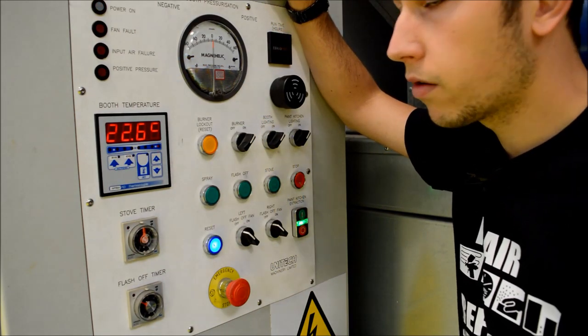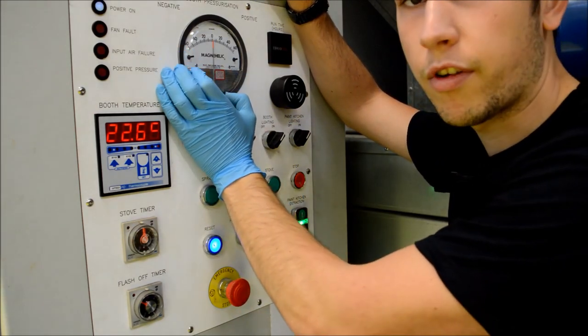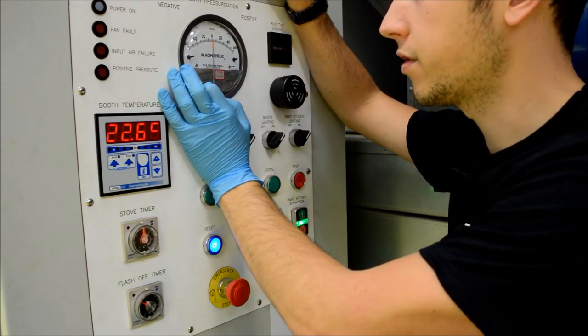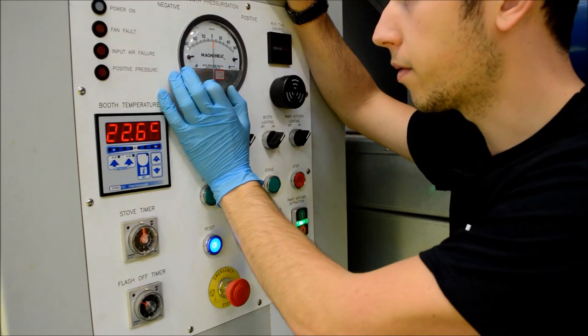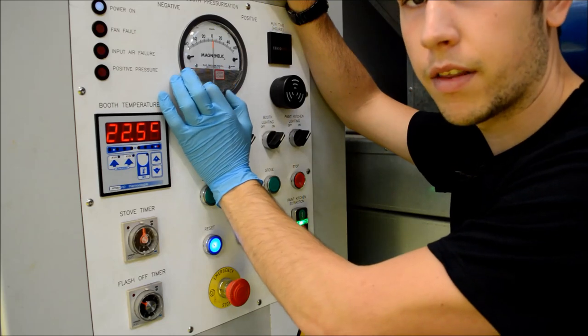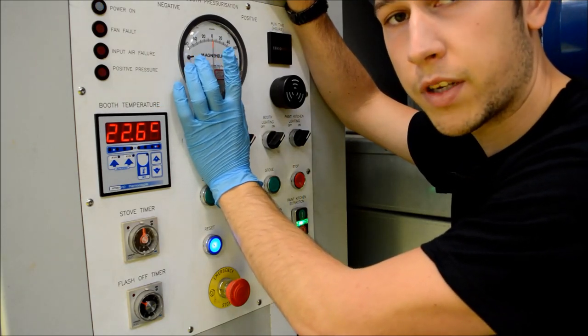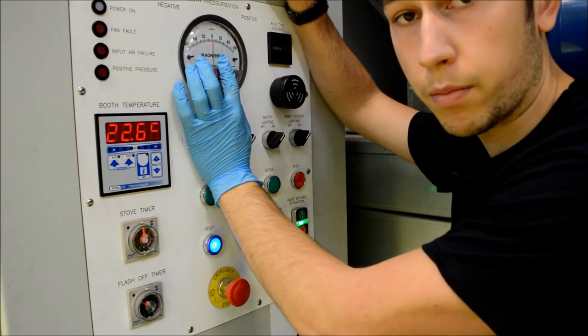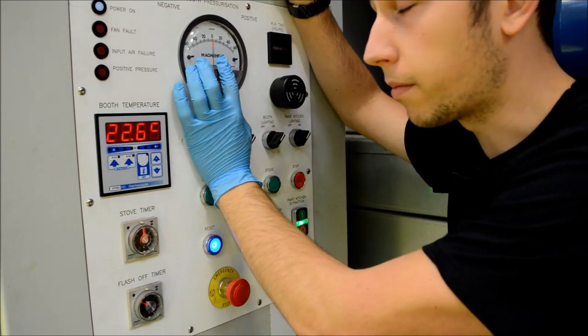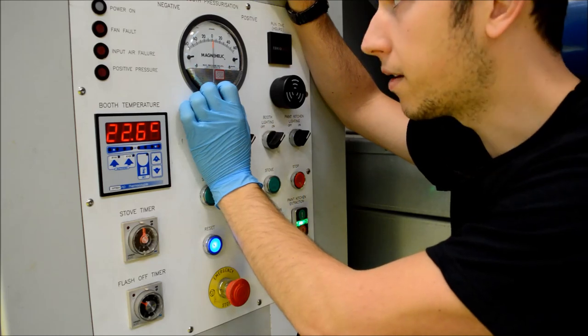So we'll just take a look at the Magnehelic gauge, and basically this shows you where we're at with the booth pressures. We've got a positive and negative pressure on here, and basically you want this pressure to be around minus 10, that's suitable for a spray booth. We don't want it in the positive because when it's positive, the booth doors are going to blow open and we're also going to get fumes from the spraying going into the workshop, which is what we don't want. The pressure in the Magnehelic gauge is measured in Pascals as well.